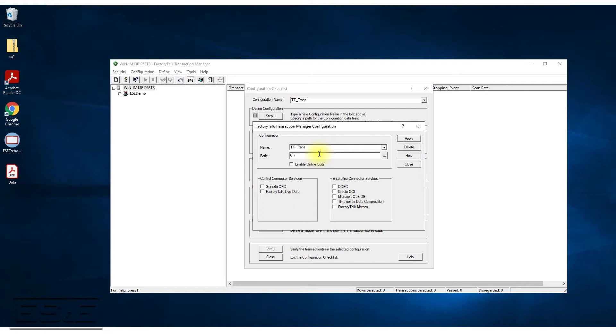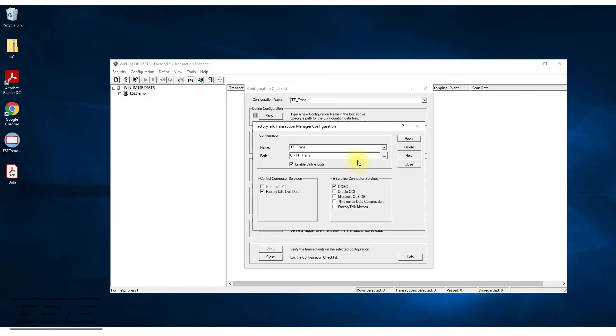Step one: tell it where you want to store it by giving it a directory location. I want to enable online editing. With Transaction Manager, you can do online editing, but the caveat is it has to be FactoryTalk LiveData — if you're using a generic OPC connection, you will not be able to use online editing. I'm going to use a standard ODBC connector, which I typically do about 95% of the time, and then do Apply.